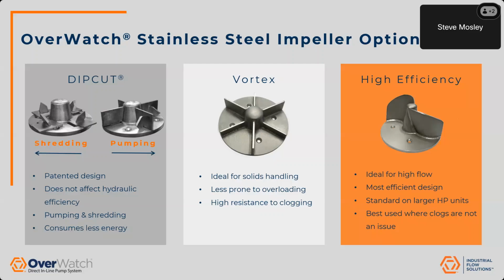Vortex impellers are generally very good for passing stringy solids, and because these pumps are handling the solids one at a time while they come down the sewage stream, you typically don't see as much risk of clogging with this as you would with a submersible lift station, where you've got a lot of the solids floating on the top of the wet well. We also offer a high efficiency impeller, as shown on the right-hand side. That is our most efficient hydraulic design and is our standard on the larger units that we offer. We've got a number of different designs on that high efficiency impeller, including the 2-vane that's shown there, as well as a few different 4-vane designs for larger flow rates and some larger heads.